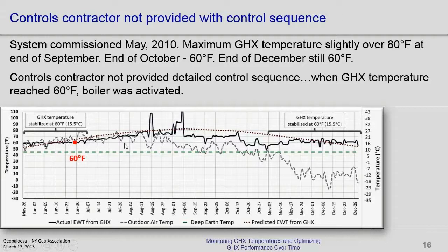Here's what ground loop temperature probably should have been. So by the end of December, we were expecting to be around 50 degrees, give or take. And when I called them up just informally at the end of December, it was still over 60 degrees. So here is the highest point that they had. Here it hit 60, and here it's still 60. And you can see what happened to the air temperature. There's no reason that it should have been still 60.